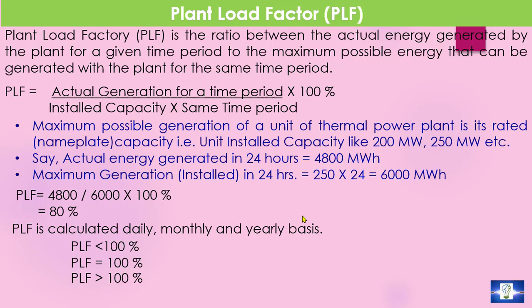If the load is maintained more than the rated capacity, then PLF may be more than 100%. But continuous generation for a long time is not possible, because it may cause different technical problems and failure of the components may be possible. So for a small period, PLF may be more than 100%, not for the long run.